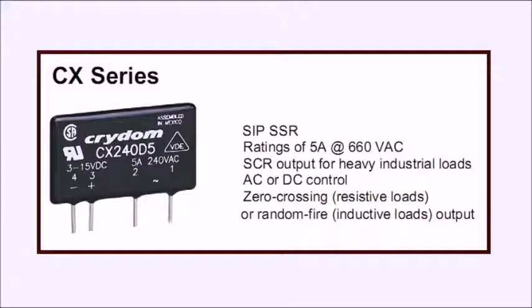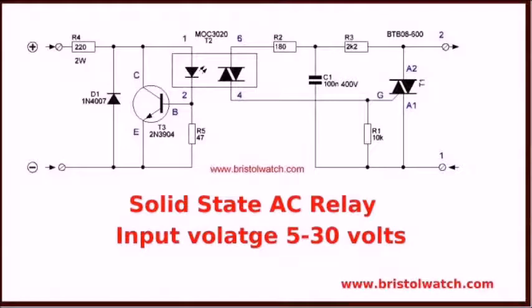Let's drop back and take a look at something else before we go on. Going all the way back to here, remember when we're using this solid state relay is for mainly resistive loads. If you're going to use inductive loads, you need a snubber circuit across the output. That was the resistor capacitor circuit you saw in my other videos and on the diagrams at the website.